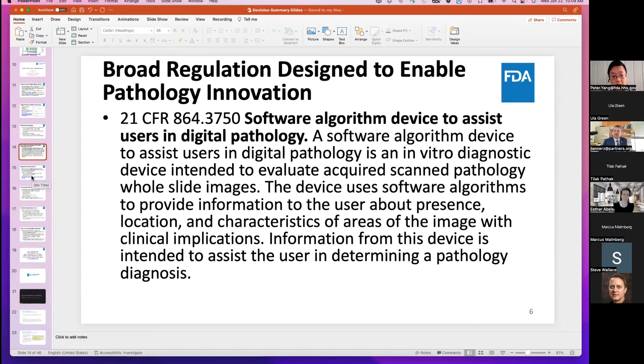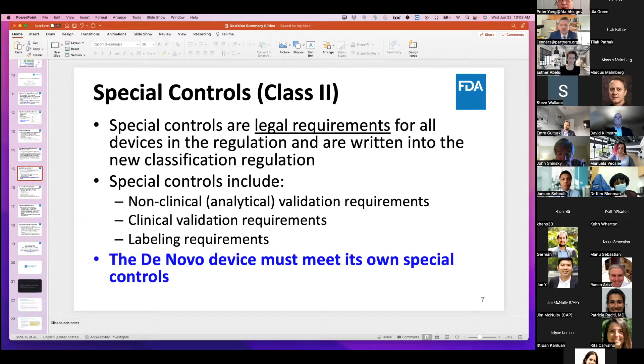As part of creating the regulation, we also create what's called special controls. Special controls are legal requirements for all devices in the regulation. They are written into the new classification regulation itself. So what I didn't show you on the previous slide was all the special controls that are listed there. And if you look at the decision summary, if you look at the granting order, you can see the special controls that are listed for this document, for this device and for devices within the regulation. Special controls can include things like non-clinical validation requirements, analytical validation, clinical validation requirements, labeling requirements, and the de novo device has to meet its own special controls.